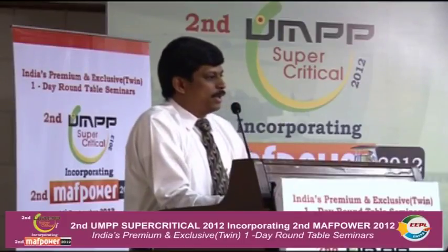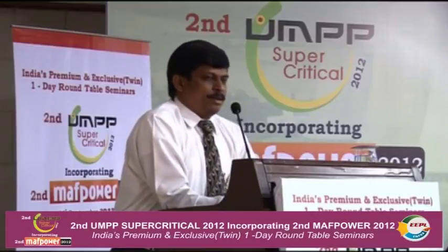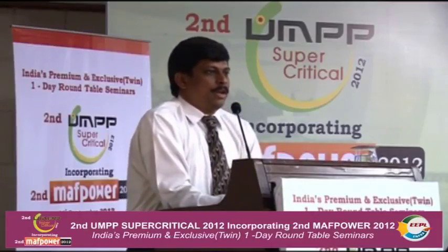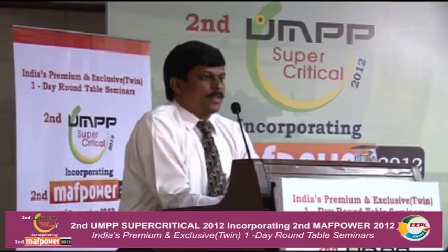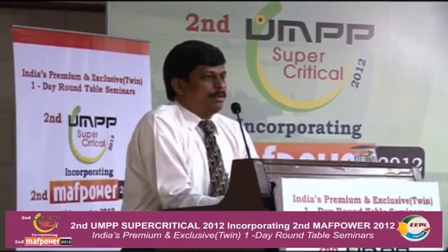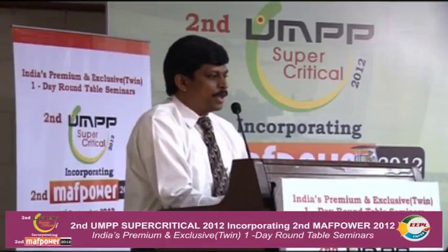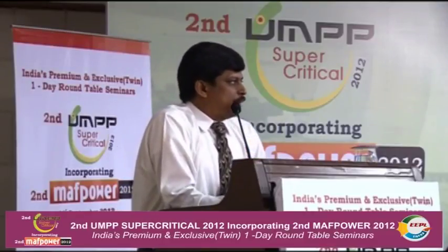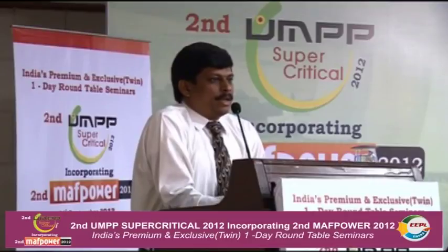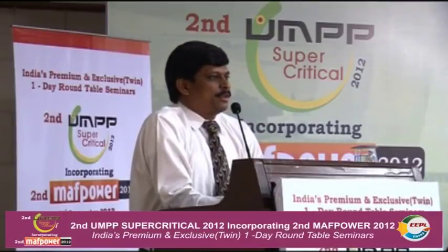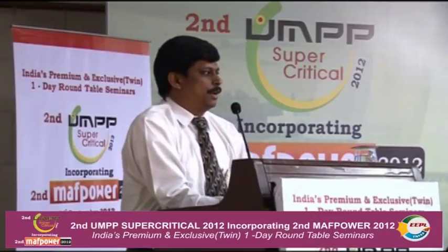The online ash meter is mounted directly on the conveyor belt, where we keep the source at the bottom of the conveyor belt and a sensor above it in the frame, and the data is transferred to the control stage. The basic principle uses the radioactive elements americium and cesium, at the bare minimum levels, which are safer than using X-ray equipment in general.